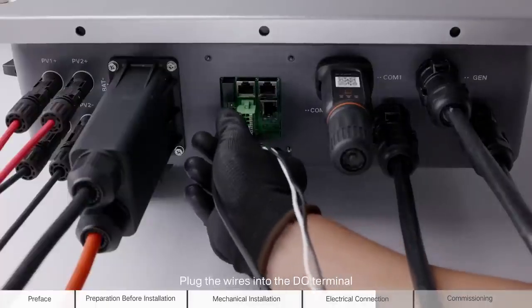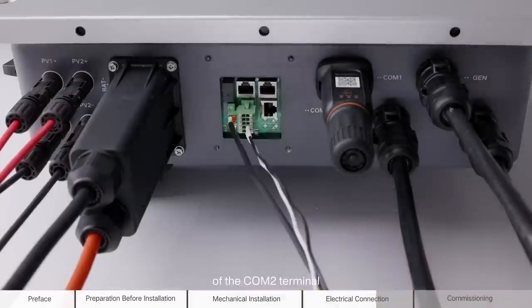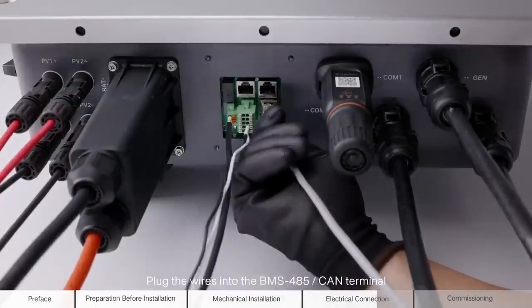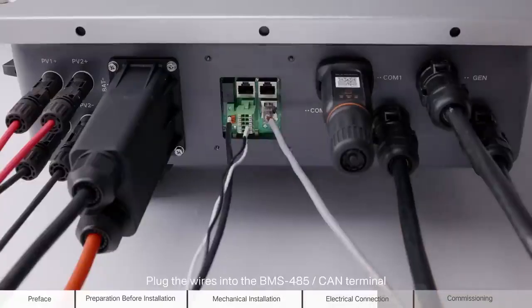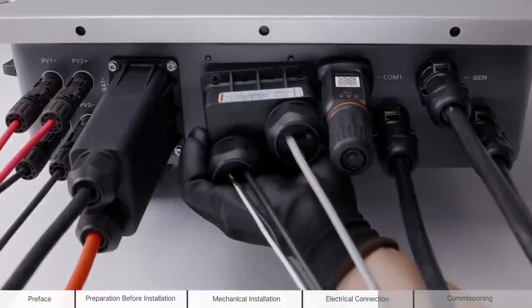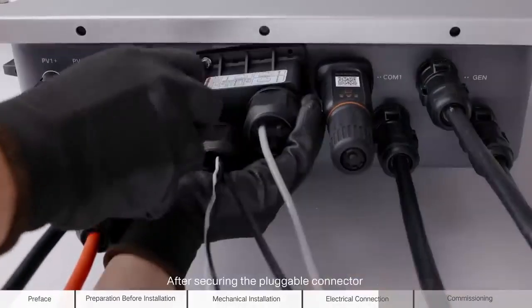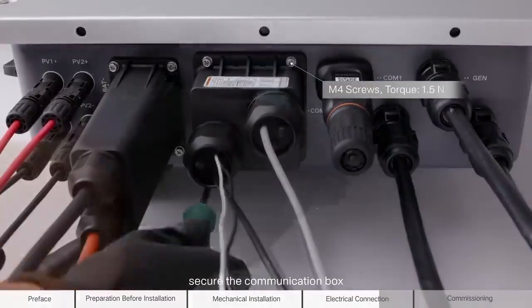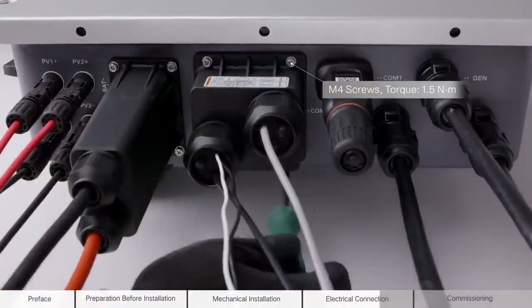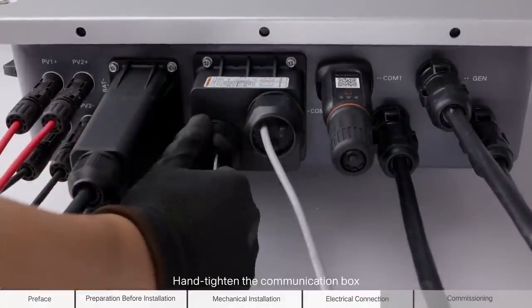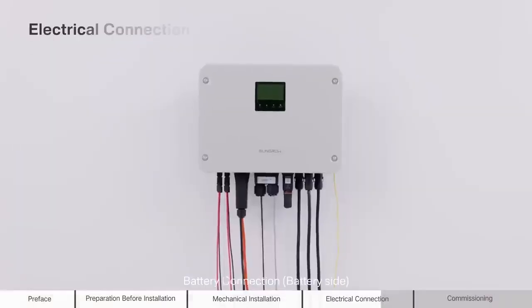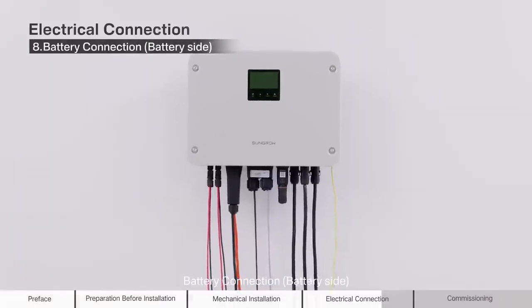Plug the wires into the DO terminal of the COM2 terminal. Plug the wires into the BMS485 CAN terminal of the COM2 terminal. After securing the pluggable connector to the bottom of the inverter, secure the communication box. Hand tighten the communication box. 8. Battery connection, battery side.